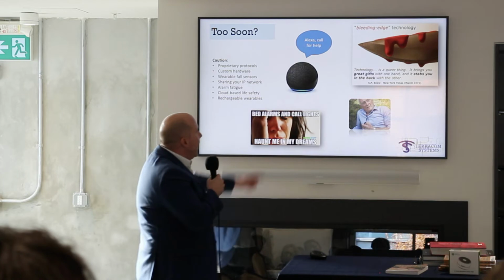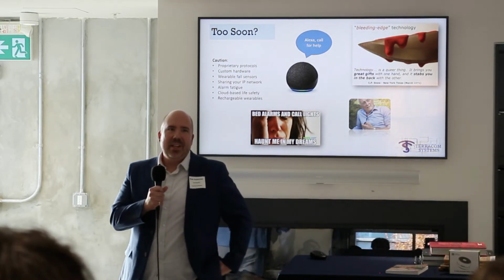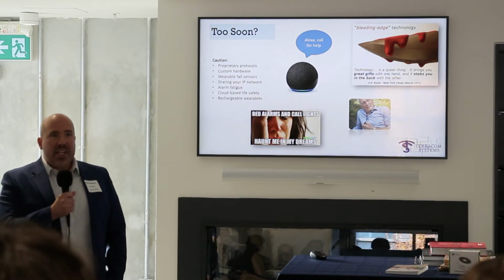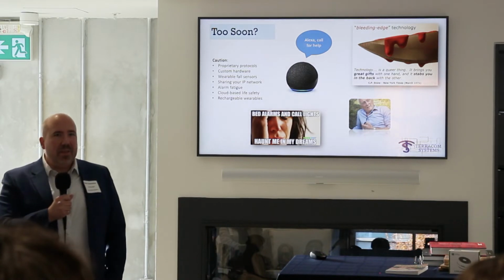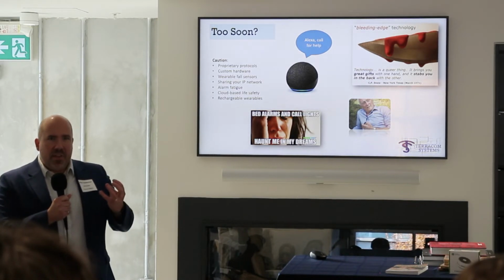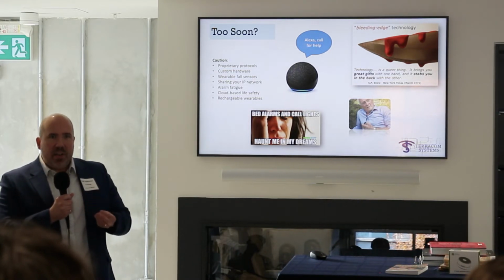Believe it or not, I actually saw this the other day, and that kind of scared me. It was an Amazon Alexa device that some nameless integrator is advertising on their website, where a resident can say, "Alexa, call for help." There are some issues with that, because I know a lot about these devices and what they need. They need a constant Wi-Fi connection, and the scary thing is they need a constant internet connection, because the voice processing isn't actually done on the Alexa itself. It sends it out to their servers to decrypt and then do the trigger from there.